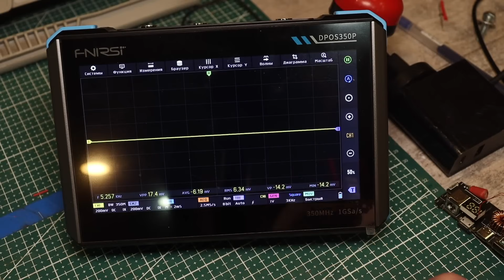We can select from the table or manually like this, which in my opinion is very, very convenient. Next is the fourth parameter. Here we can set the oscilloscope's resolution. The sampling rate is also displayed here. This parameter is not selectable because the oscilloscope manages this value automatically. Any digital oscilloscope only uses the maximum sampling rate in the upper frequency range. So, if you are analyzing some slow processes, the sampling rate will be minimal.